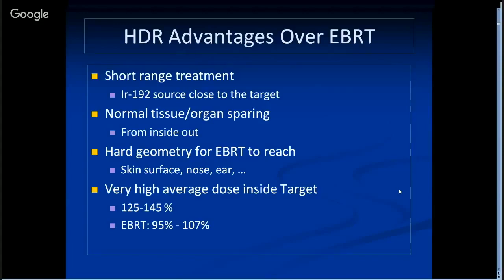Another important difference between HDR and EBRT is the very high average dose inside the target, which can be like 150% of the prescribed dose. But for external beam, you get a pretty flat dose, like 95 to 110%.